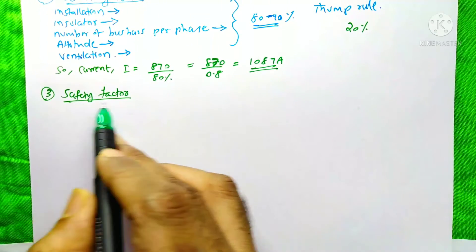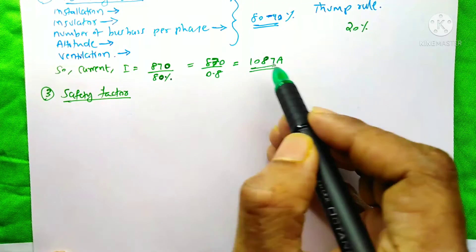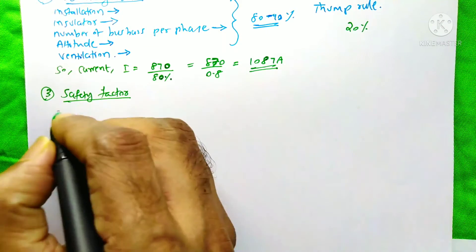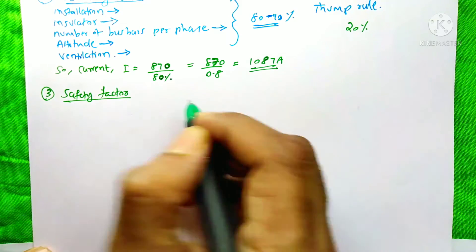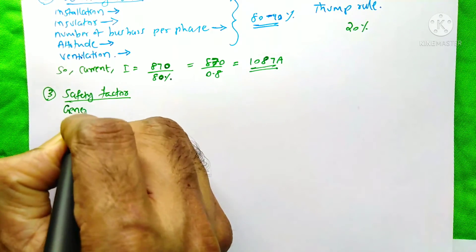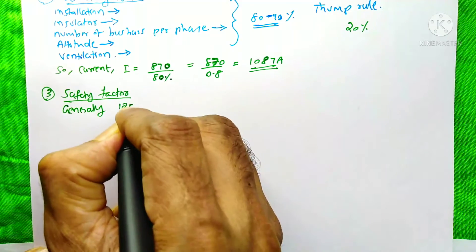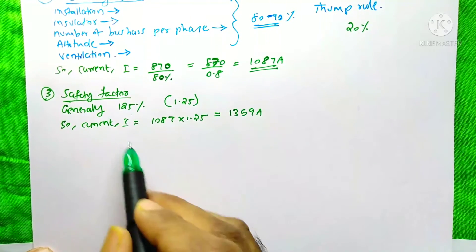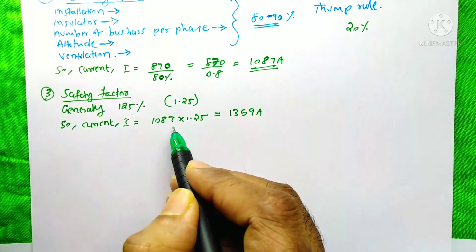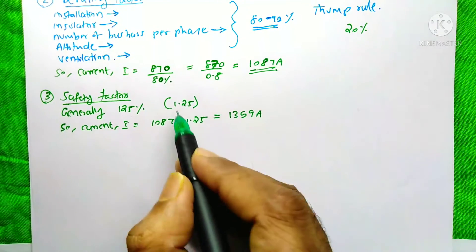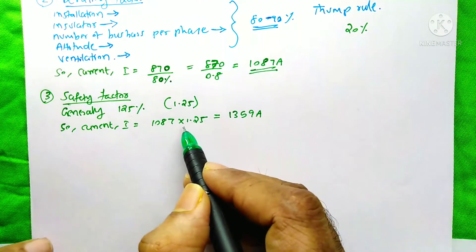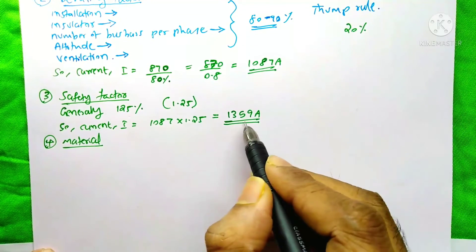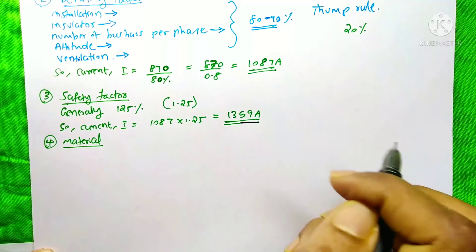The next step is applying the safety factor. The 1087 amps does not yet include a safety margin. We generally use a safety factor of 125% in the industry — a factor of 1.25. So 1087 × 1.25 = 1359 amps. With this step, the current calculation is complete.